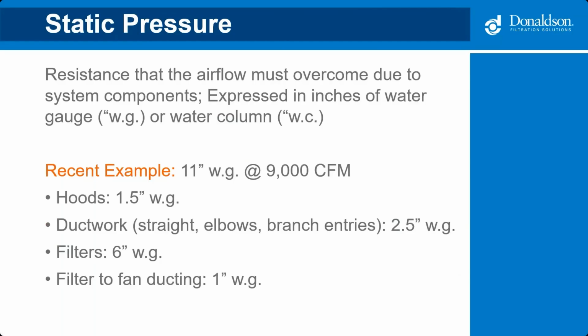Here's an example from a recent system that we designed. The hoods totaled 1.5 inches of water. The ductwork, including straight runs of duct, elbows, branch entries, totaled about 2.5 inches. The filters in the collector totaled 6 when completely dirty. It's the worst case scenario. And the filter to the fan ducting was about 1 inch. So the total system static pressure for this particular project was about 11 inches worst case scenario.